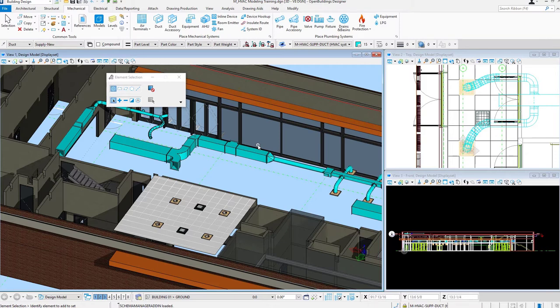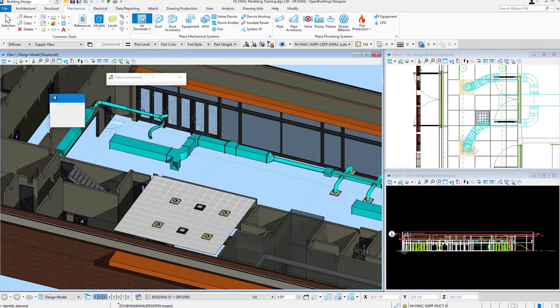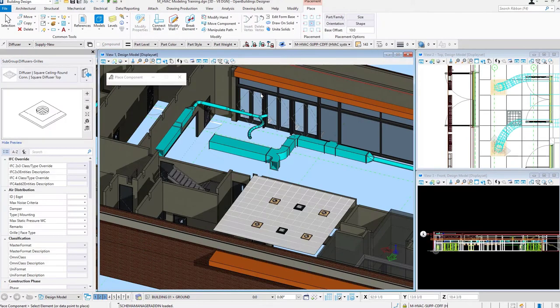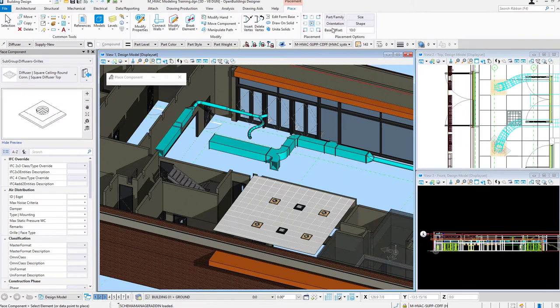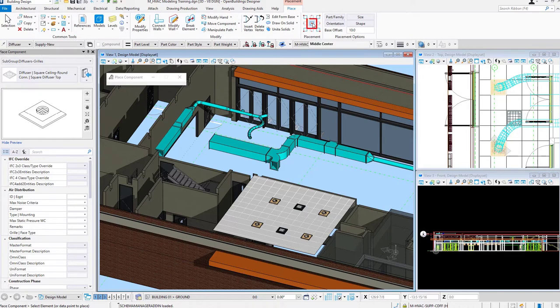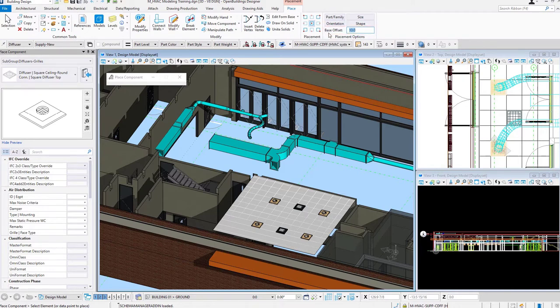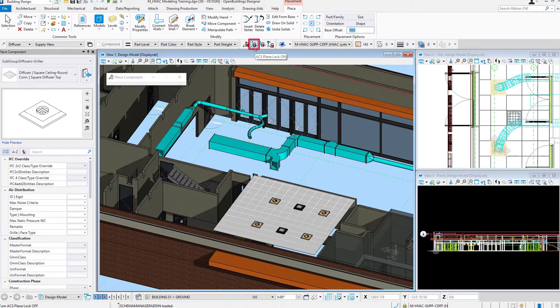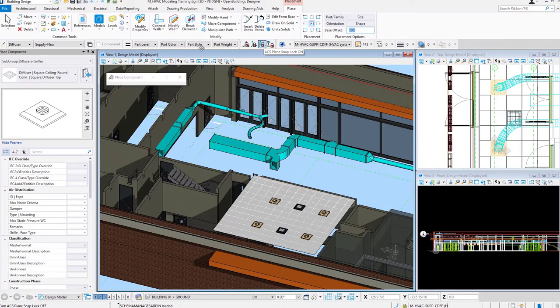So I'm in my model, I'll come up to the Mechanical tab, select my Air Terminals tool. The Property Panel opens up. I'll double check my placement options. I'll be placing this air terminal by the middle center point here. I have part family orientation size and shape turned off. My base offset is set to 10 feet. I do have my ACS Plane Lock and ACS Plane Snap Lock turned on.